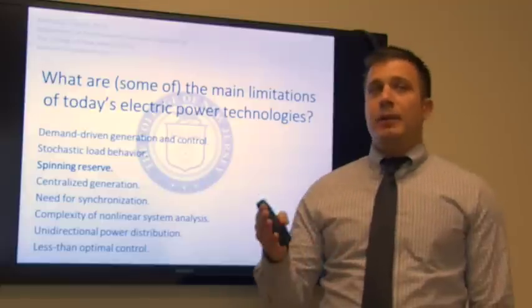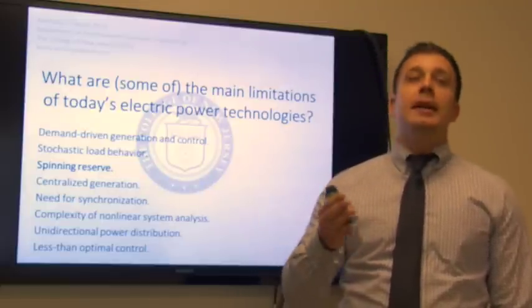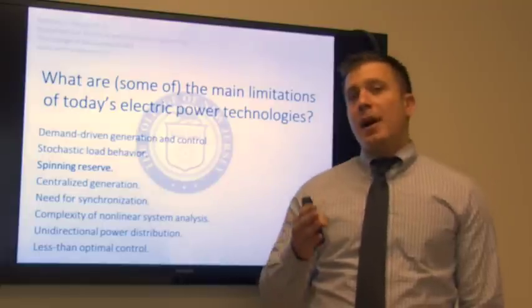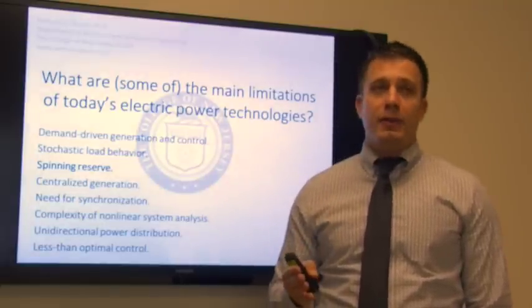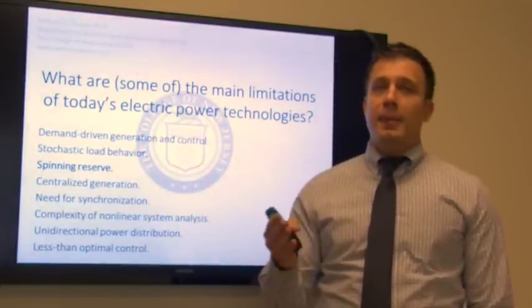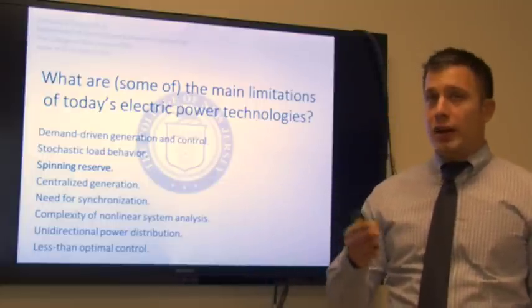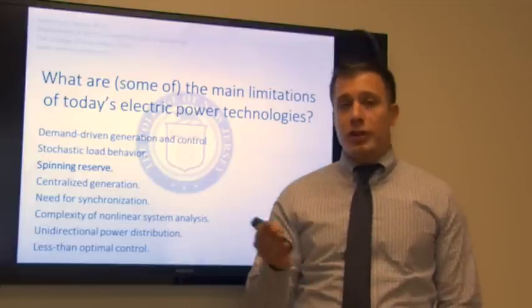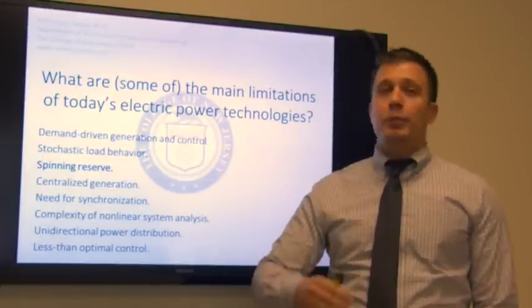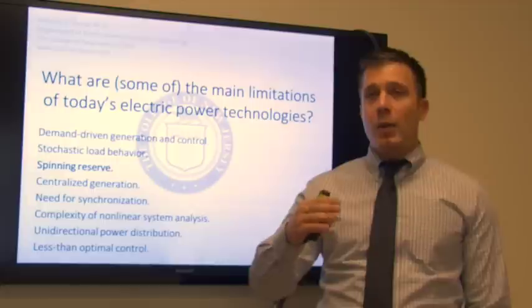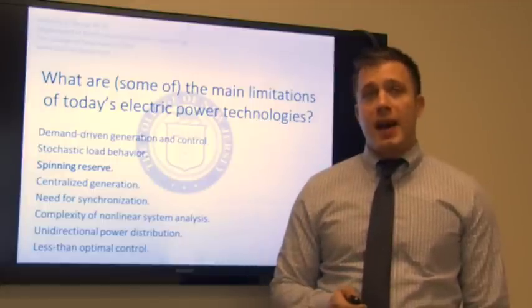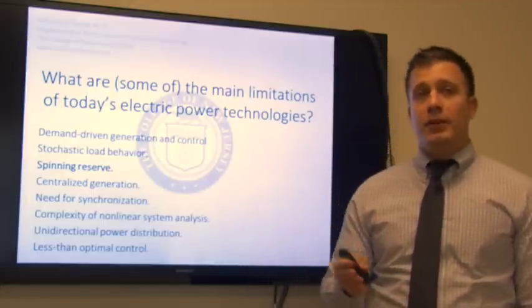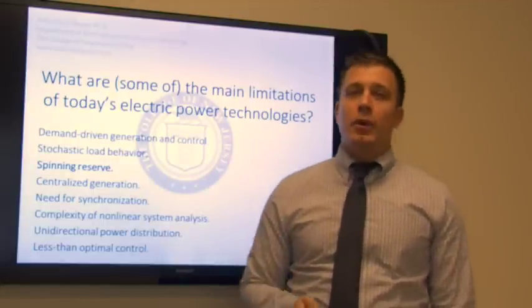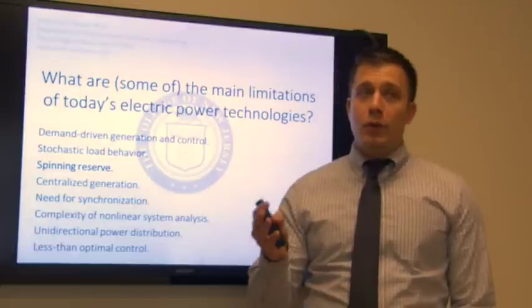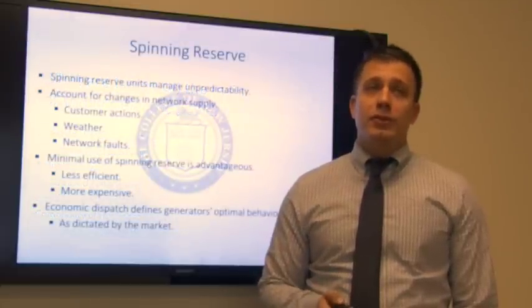Next is spinning reserve, or more appropriately, the need for spinning reserve. Because power systems exhibit unpredictable behavior, a balance between supply and demand can't be maintained by traditional generators alone. What I mean by traditional generators is one that's set to output a certain number of megawatts and it remains static. Other units with the ability to quickly increase and decrease their real power output via fuel throttle control are referred to as spinning reserve.